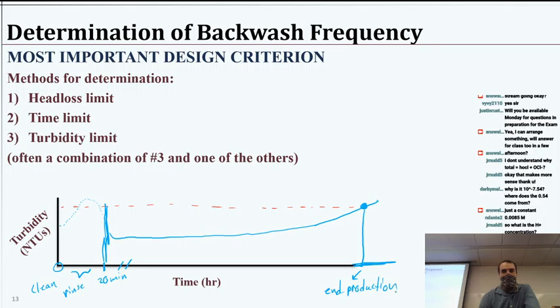So everything between the rinse stage when that ends and at this point, we're producing water. Then after that, we stop and we have some sort of backwash. So whatever happens between there some time, and then we start over. So we'll say from here would be the next cycle. Okay, so that's kind of a typical timeline, and that's what it would look like for the turbidity. That rinse stage, again, is too dirty to use, so we don't use that water. And then as we get going for the next, I don't know, something like up to 100 hours worth maybe, anywhere between 24 and 100 hours, something like that might be typical. We have operation, then we stop it for backwash.